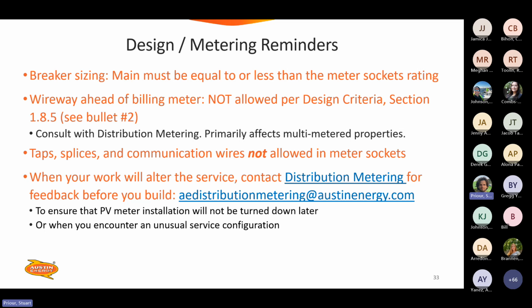So some reminders about metering and design: your main breaker has got to be equal to or less than the meter socket rating. So if you see a 320 amp meter can, for example, with a 400 amp disconnect behind it as the main service, not related to solar, that will be something that you'll have to take into account to either repair or upgrade so that you can have the solar installed and inspected and not have any issue with the existing meter. A wireway ahead of the billing meter is not allowed per our criteria.